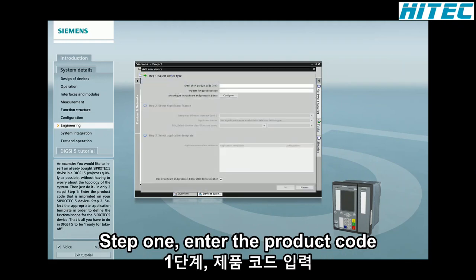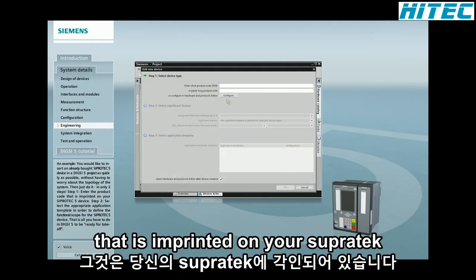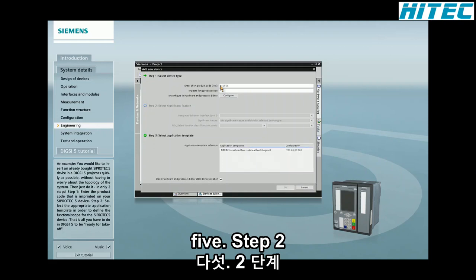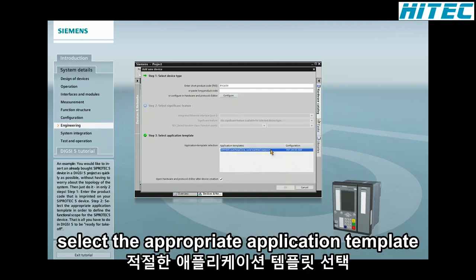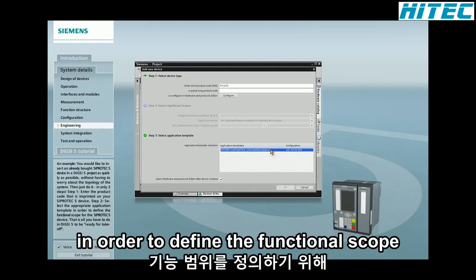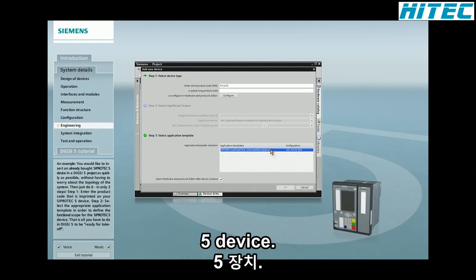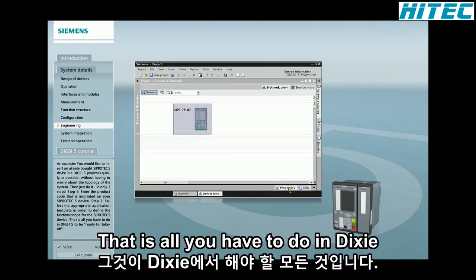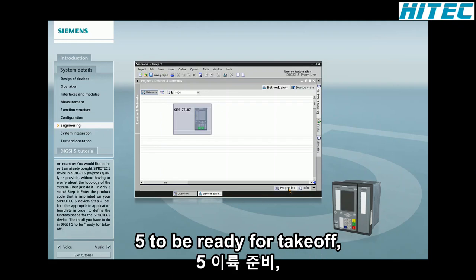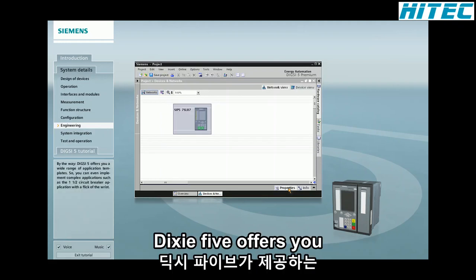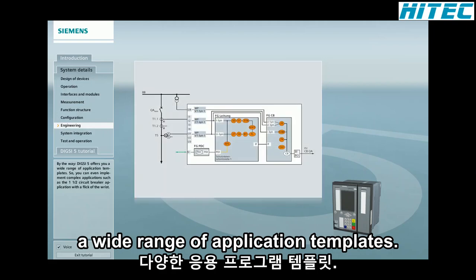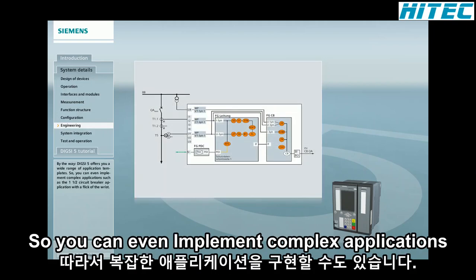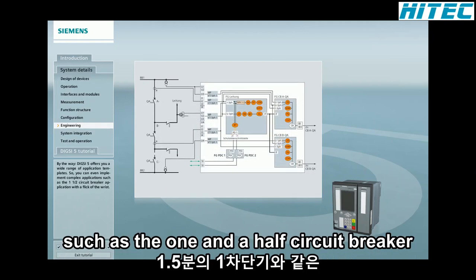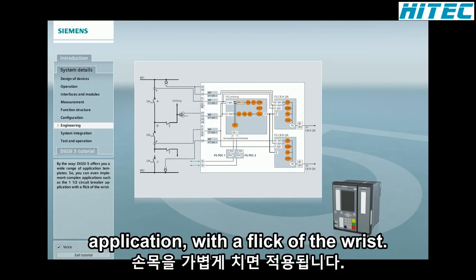Step 1. Enter the product code that is imprinted on your SIPROTEC 5 device. Step 2. Select the appropriate application template in order to define the functional scope for the SIPROTEC 5 device. That is all you have to do in DIGSI-5 to be ready for takeoff. By the way, DIGSI-5 offers you a wide range of application templates, so you can even implement complex applications such as the one-and-a-half circuit breaker application with a flick of the wrist.